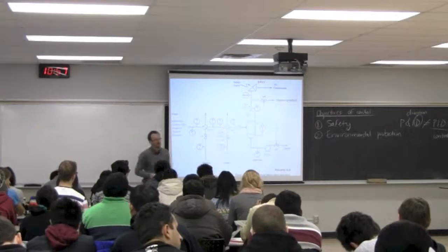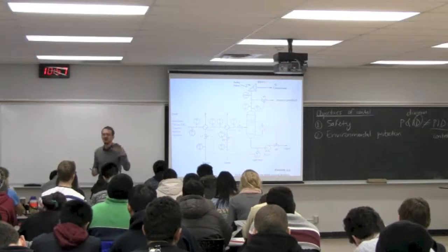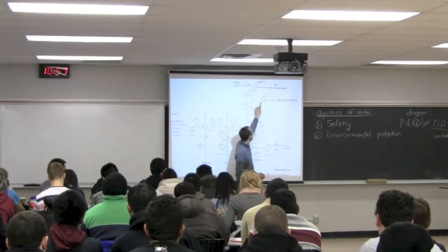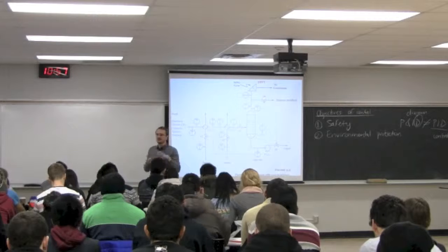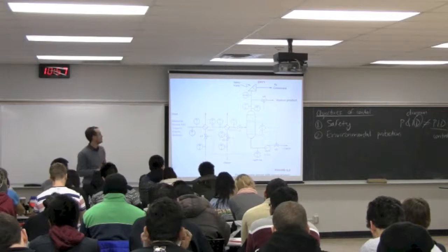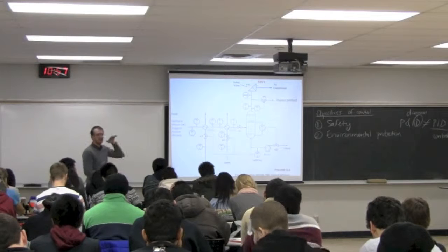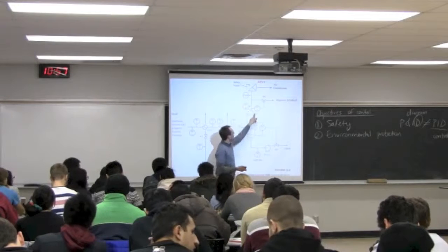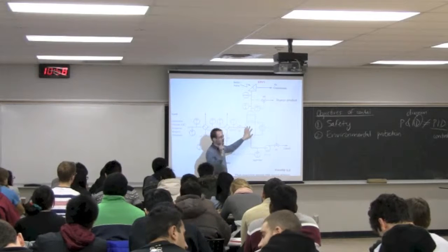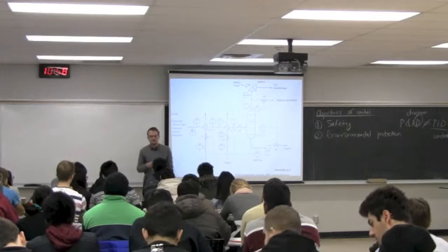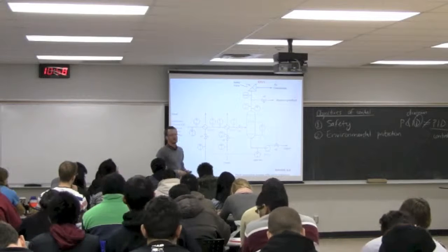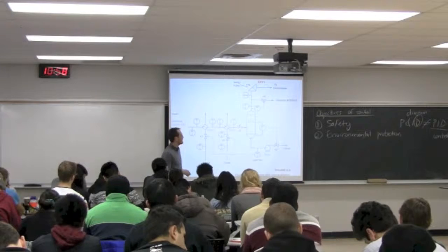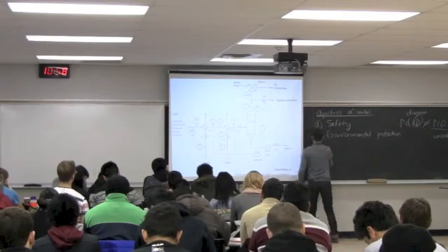So we have SRV1, safety relief valve 1. These are valves that are absolutely mechanical. Not a single electrical signal is involved. There may be all sorts of electronics and pressurized piping over here to make the system work, but SRV1 is fully mechanical. It's just springs. These are things that are not going to fail on us, or have an extremely low probability of failure. That valve will open at a certain threshold pressure which we set. We set it so that it will open below the pressure at which this tank will burst. So if this tank will burst at, say, 300, we set that valve at 280. Okay? So it will open at 280 and move the material to a contained vessel where we can treat it, before that vessel explodes and injures us and injures the environment. So environmental protection. Okay, SRV1 is also a form of equipment protection.